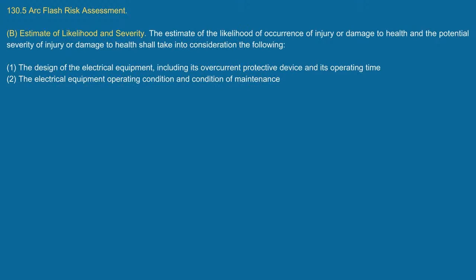But that's 18 inches. And then there's two other things that you need to know. You need to know what the arc duration is. What's the clearing time of that overcurrent device in seconds? And then the other thing you're going to need to know is what is the short circuit current rate, okay? Now, when you look at the clearing time, there could be a massive difference between some of these overcurrent devices, where one would clear at a quarter cycle and one would clear at 3 cycles.